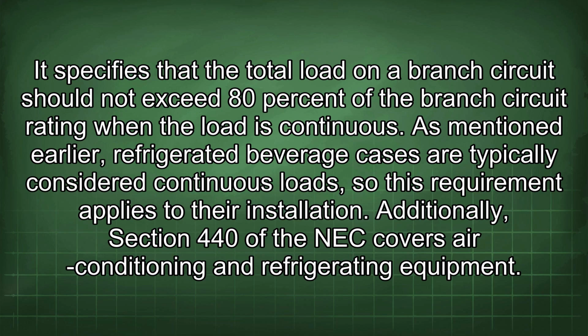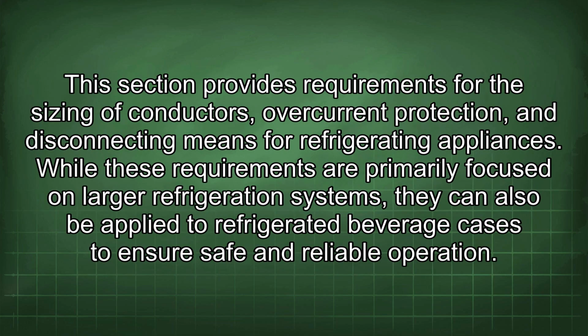As mentioned earlier, refrigerated beverage cases are typically considered continuous loads, so this requirement applies to their installation. Additionally, Section 440 of the NEC covers air conditioning and refrigerating equipment. This section provides requirements for the sizing of conductors, overcurrent protection, and disconnecting means for refrigerating appliances. While these requirements are primarily focused on larger refrigeration systems, they can also be applied to refrigerated beverage cases to ensure safe and reliable operation.